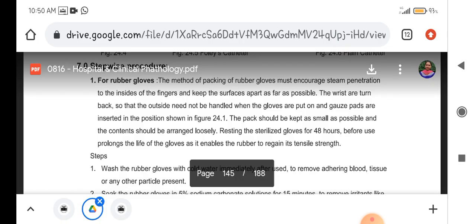Now for rubber gloves, you must encourage steam penetration to the inside of the fingers and keep the surfaces apart as far as possible. Okay, meaning the fingers of the hand gloves should be kept separate, so that the steam will penetrate into the fingers of the hand gloves. Okay, the wrists are turned back so that the outside need not be handled when the gloves are put on, and gauze pads are inserted in the position as shown in 24.1.